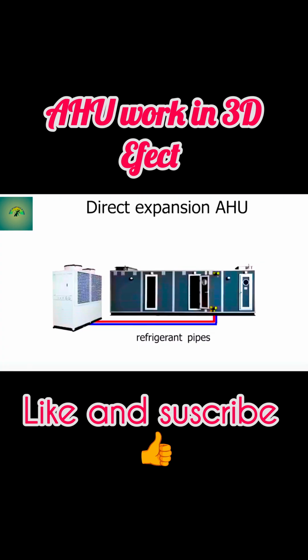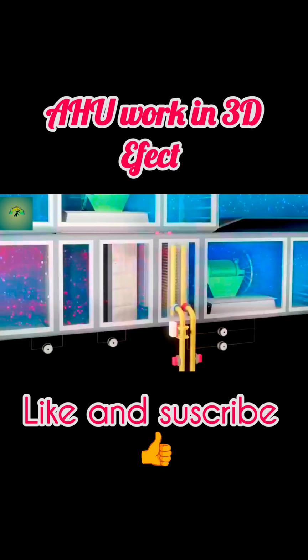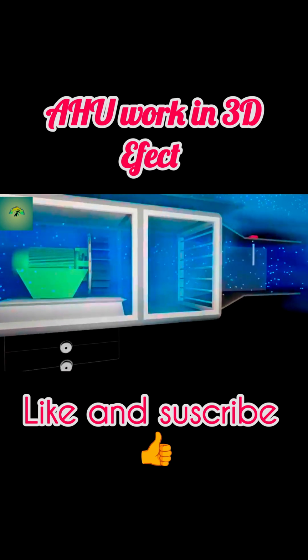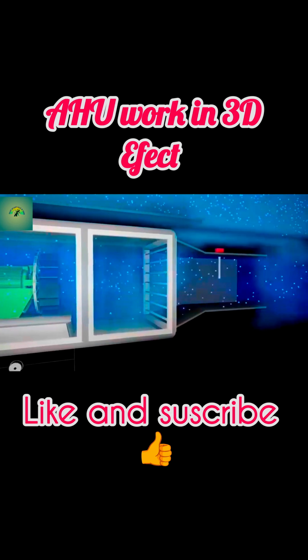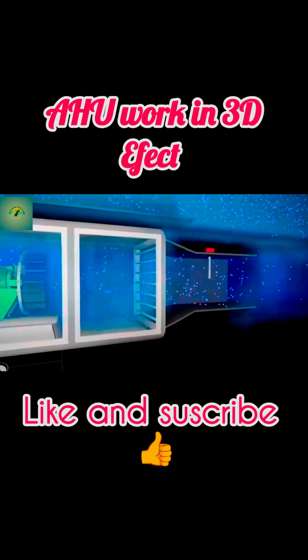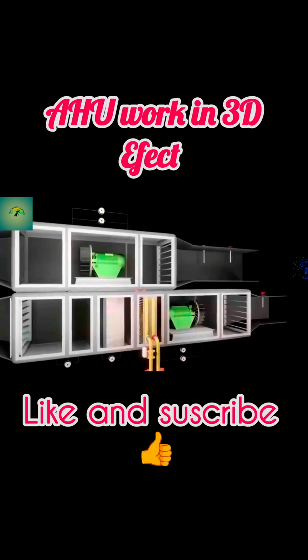Direct expansion air handling units have refrigerant that flows through the coil. The refrigerant directly exchanges heat with the air blown by the fan. Lastly, the clean, conditioned air is pushed out of the air handler into the enclosed space. The fan in the air handler draws unconditioned air from an enclosed space.